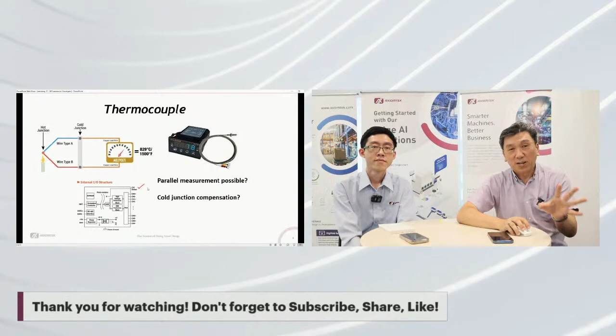For example, if you've gone through some of our sessions before, you can use our IoT Edge gateway, and also our 4G router gateway that can fit this Modbus TCP. Sometimes you may be using Modbus RTU, but what happens if you don't have a Modbus interface? Some devices don't have a Modbus interface - they give you a 4-20mA signal, and you can use a different module, a 4-20mA module, that allows you to do the measurement.